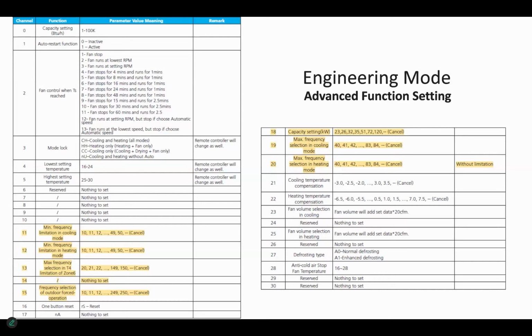Okay, so it increases that temperature. It also reduced a time window on one of our defrost conditions from 120 minutes down to 70 minutes, as far as when it looks to defrost. It did that, and then there was a third change. I can't remember exactly what it was, but they've changed some of those parameters.